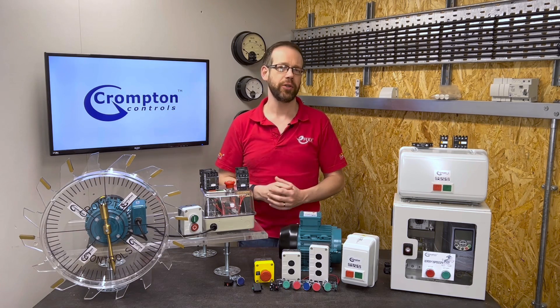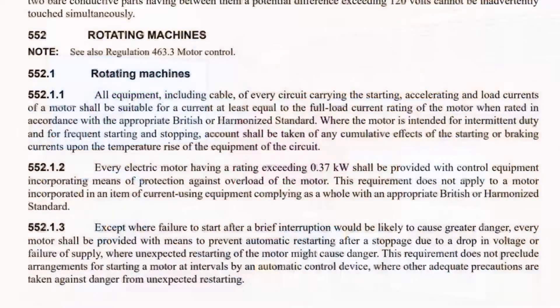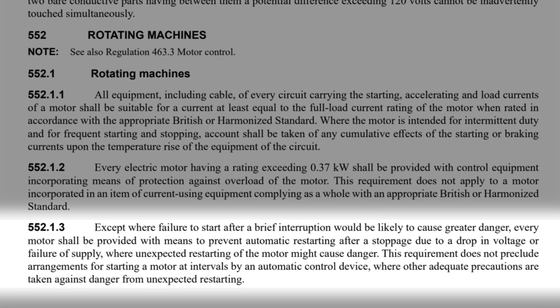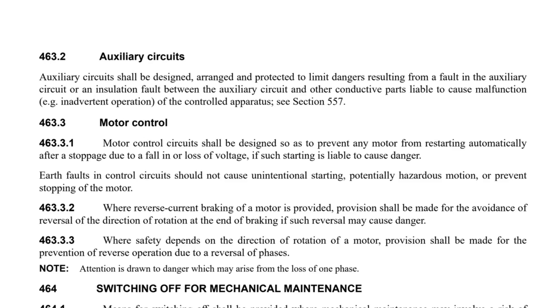There are two regulations that are very similar to each other. One is in 552.1.3 in the section on rotating machines. It reads: except where failure to start after a brief interruption would be likely to cause greater danger, every motor shall be provided with means to prevent automatic restarting after a stoppage due to a drop in voltage or failure of supply, where unexpected restarting of the motor might cause danger. This requirement does not preclude arrangements for starting a motor at intervals by an automatic control device where other adequate precautions are taken. The other is found in 463.3.1, which relates to motor controls and is so similar that we won't reread it here.